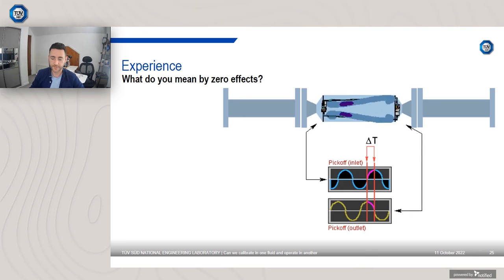However, in an ideal scenario, with zero flow, you'd have zero delta T and ultimately zero mass flow being recorded, but you don't. You have what's known as zero effects. As the meter is installed, you still get a slight out of phase between the two pick-offs, and that results in a perceived mass flow rate when there's zero flow. This is what the zero effects are. So you want to try and account for these and remove them by performing a zero procedure. You would check your zero, check if it's out of the specification, zero it, and ultimately this should ideally then account for it. And if you perform a calibration, zero effects shouldn't be significant.